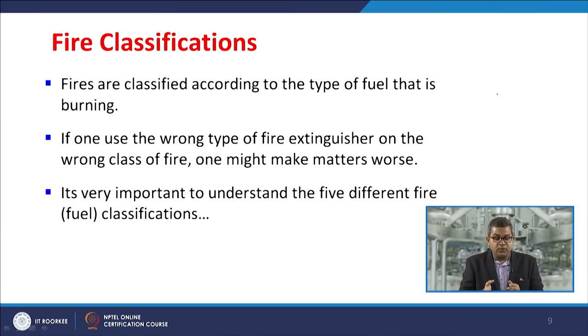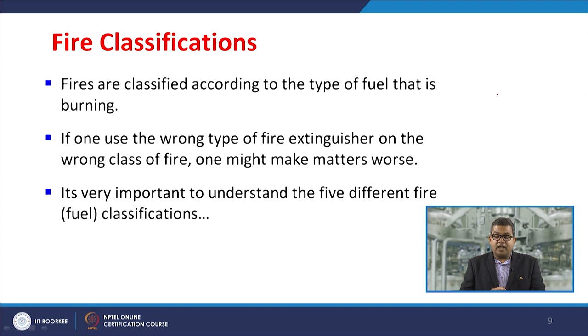Let us look at fire classification, because in day-to-day affairs you may encounter different types of fire — fire through electrical circuits, fire through chemical runaway reactions, or domestic LPG combustion. Fires are classified according to the type of fuel that is burning. If you use the wrong type of fire extinguisher on the wrong class of fire, you might make matters worse. For example, if you try to extinguish a cooking oil fire with water, the scenario would be extremely destructive, as the oil will spatter out and cause more danger.